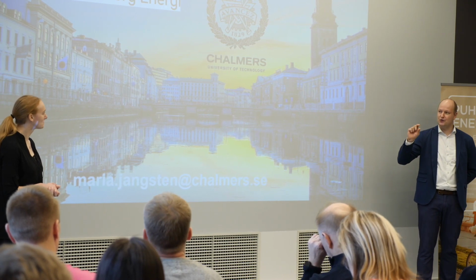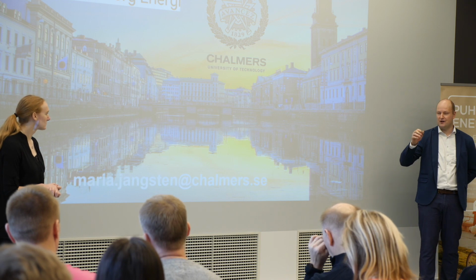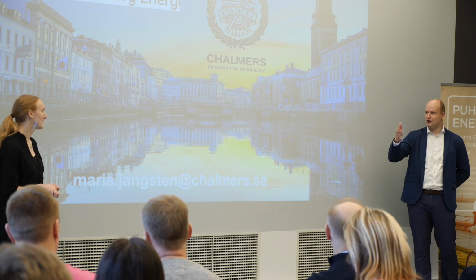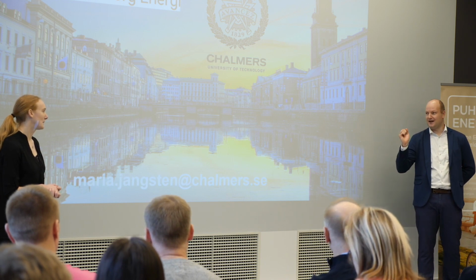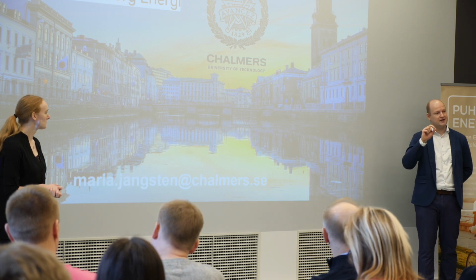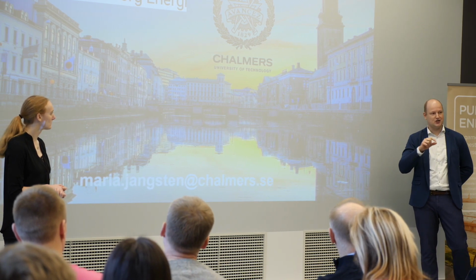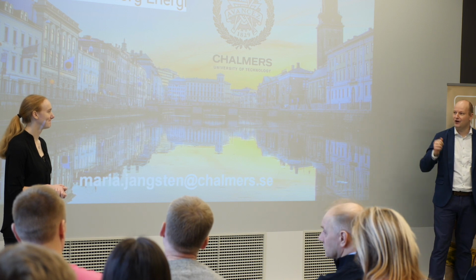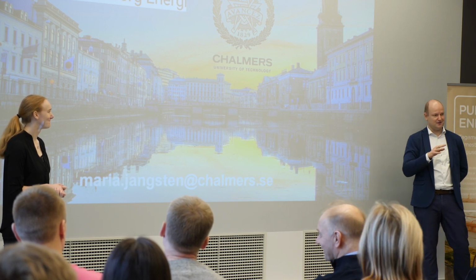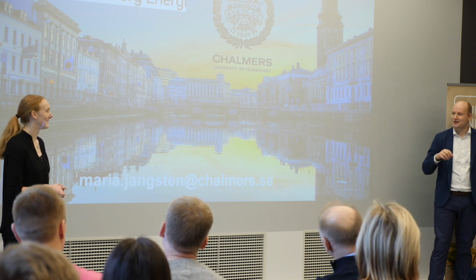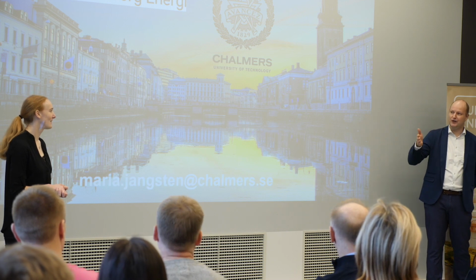You didn't want to lose any degrees, because if you put in a heat exchanger, from the river you get 5 degrees, and with the heat exchanger maybe you lose 1 degree, 1.5 or something like that. This was an open system, and actually this water was damaging the devices. So this was a problem, and your colleague said please don't make this mistake in Estonia. So now you put the heat exchanger there.